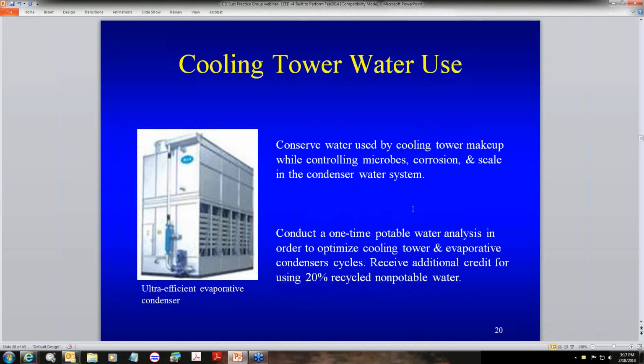Cooling tower water use is important, because often in building projects the cooling tower water usage is more than the entire rest of the building. The goal is to conserve water use by cooling tower makeup while controlling microbes, corrosion, and scale in the condenser water system, and to conduct a one-time potable water analysis to optimize cooling towers and evaporative condensers. This means that if the water is still somewhat clean, it recycles through the cooling tower instead of being dumped down the sewer. An example is shown here on the left: an ultra-efficient evaporative condenser.